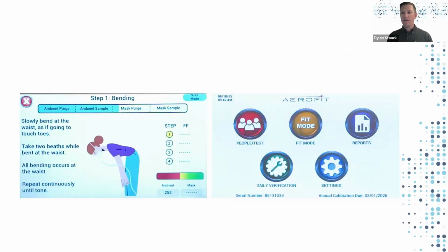So when we look at the user interface, this is what it looks like. These are actually two screenshots of the screen of the AeroFit. The first one is what it looks like when you are actually fit testing. So you'll see written instructions on the left, clearly defined written instructions that mirror what is called out in the standard. So Dr. Lynch went through and looked at the standard and made sure that our verbiage met what the standard was asking, and that it was easy for the fit test subject to comprehend while they were doing it.